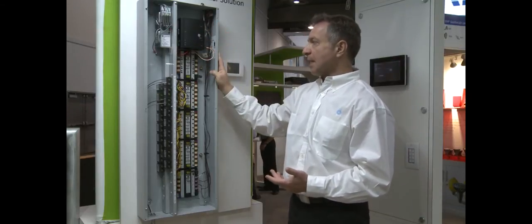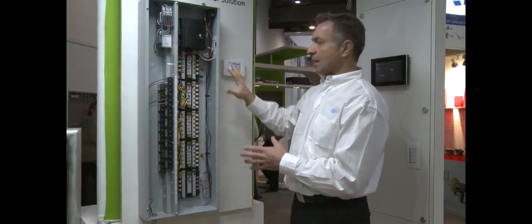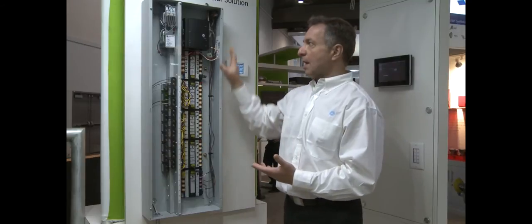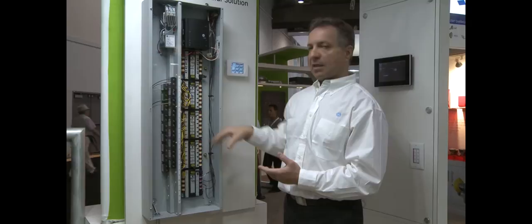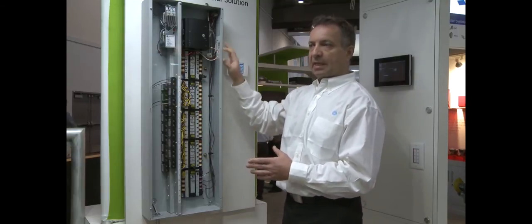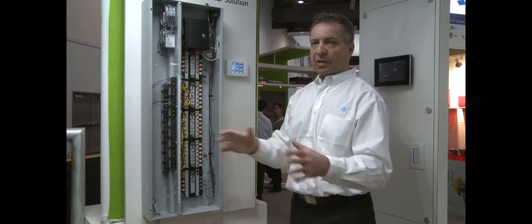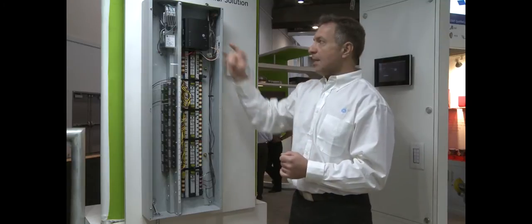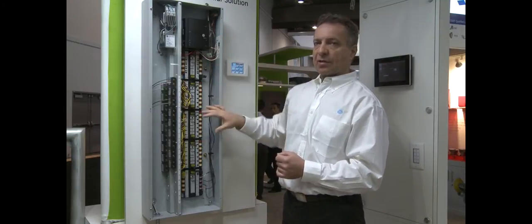The nice part of it is like a system could be installed in smaller application using a touch screen that allows to do the full programming. Then if needed to add the BACnet controller, whenever this is plugged in, it will learn the whole network configuration. So it doesn't have to be programmed, just plug in, it learns the whole network and then the information is brought on the computer. You can just change anything through the software. Information resides, is redundant, resides in the controller and also in the field devices. So pretty safe from that point of view for failures.